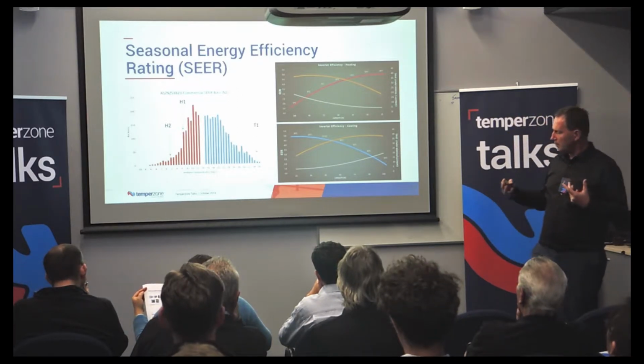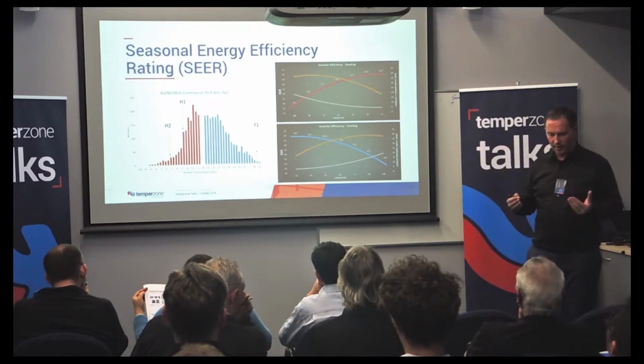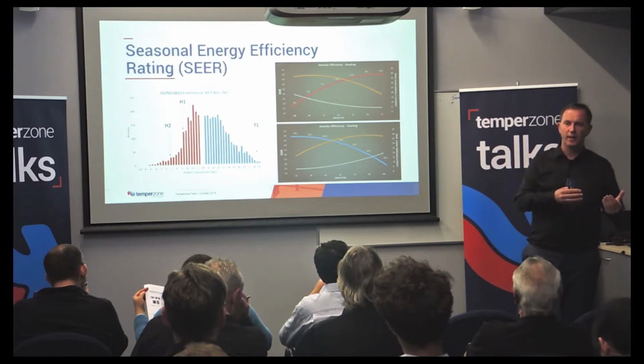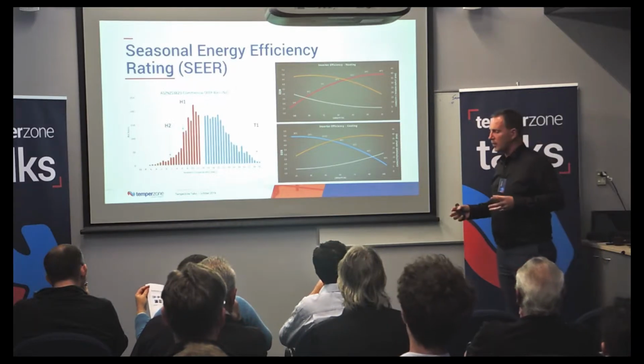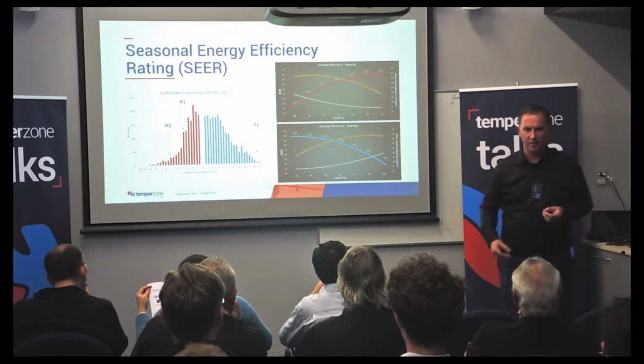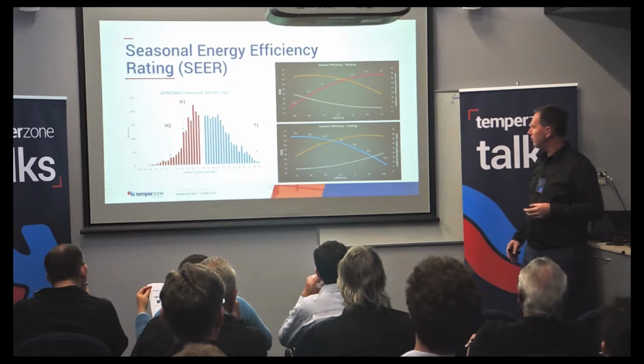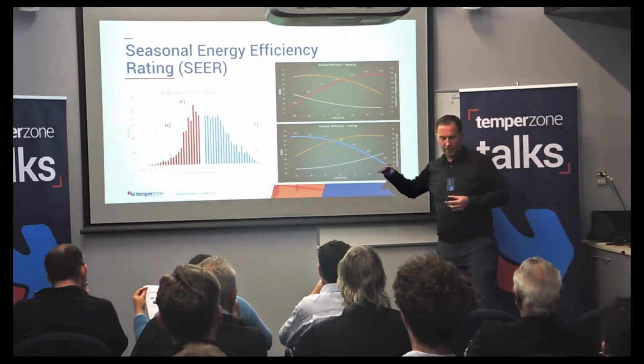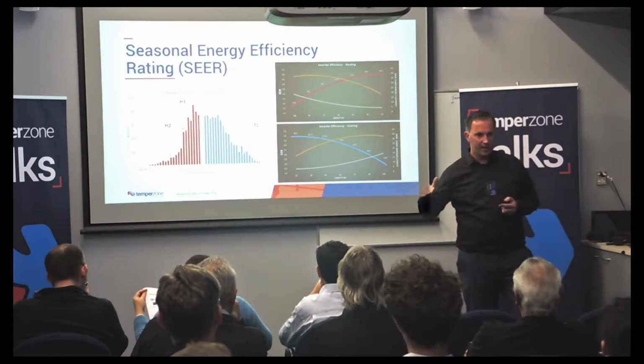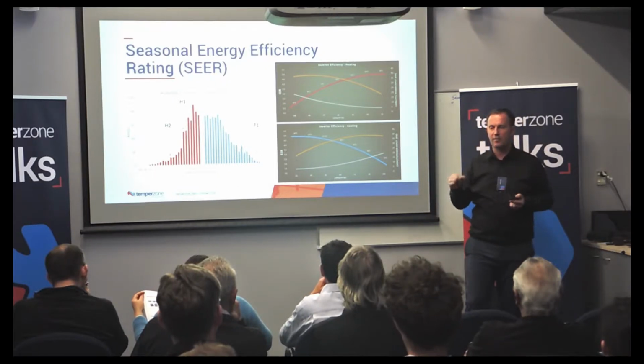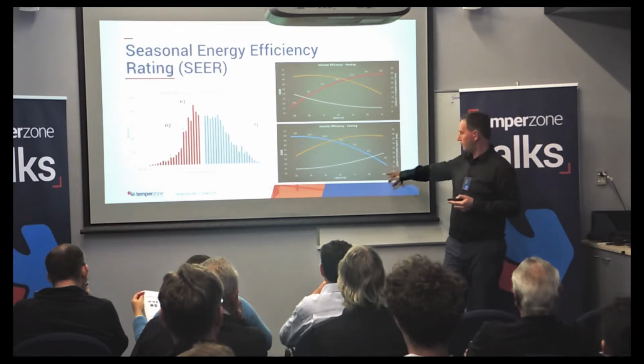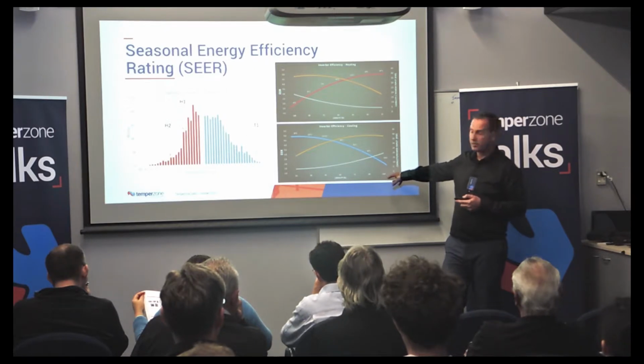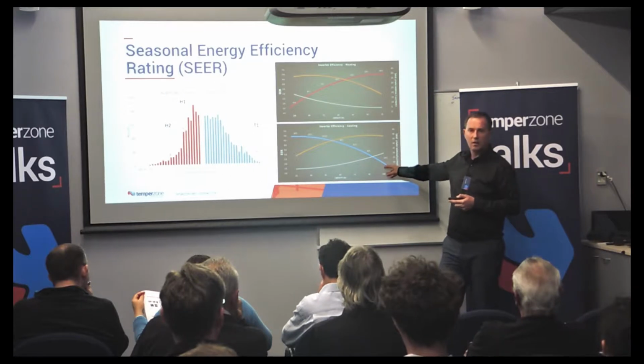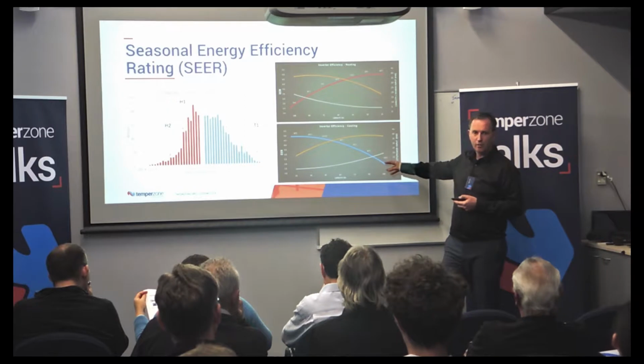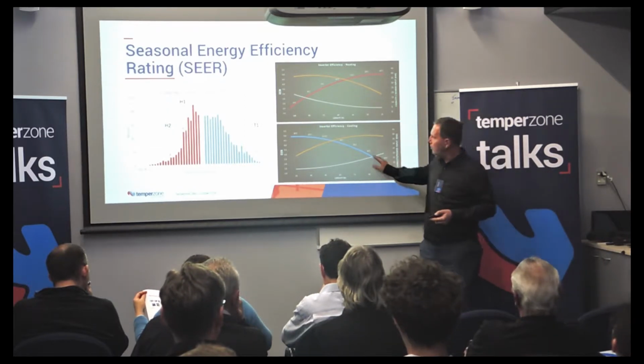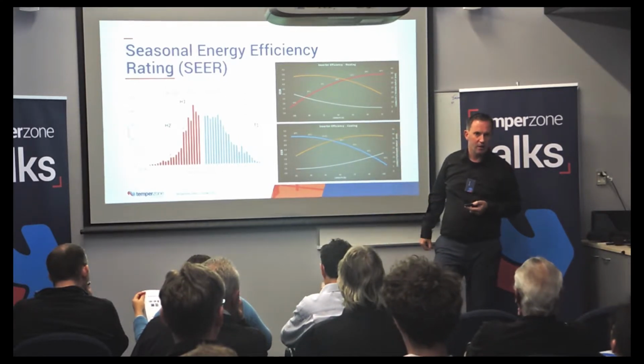When you look at the impact of part load on system efficiency, it's not just that the compressor is more efficient as it works more slowly; the load on the compressor is much less too. This isn't a standard, but if you approximate the speed a compressor needs to run at to meet a given heat load, and look at the effect on efficiency, you can see that in cooling, on a really hot day, the compressor has to run flat out and your efficiency is relatively low. As conditions become more mild and the compressor slows down, you get a very significant increase in the efficiency of these systems.